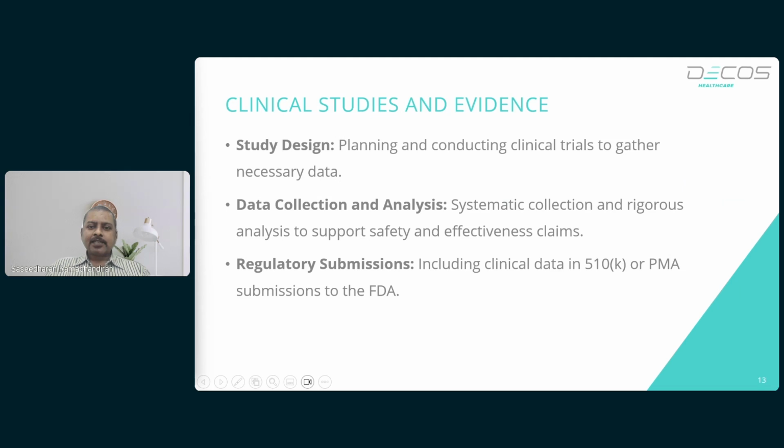Since clinical evidence plays such an important role in pre-market approval, let's dive deeper into the studies and data required to meet these regulatory demands. Clinical evidence is essential to demonstrate device safety and effectiveness, with the structure of study design, data collection and analysis, and regulatory submissions. For study design, clinical trials must be robust and well planned to gather reliable data. For data collection and analysis, rigorous data analysis is performed to support safety claims. And for regulatory submissions, clinical data is submitted as part of either the 510(k) for substantial equivalence or PMA for the high-risk device process.